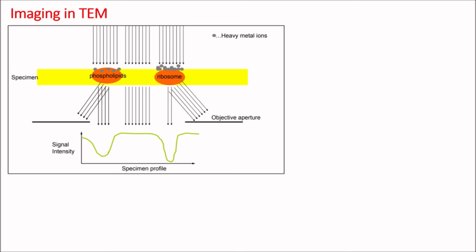Absorption of electrons would result in heat damage of the specimen if it is heat sensitive. At high magnification, at which a small area of the specimen is exposed to high radiation, beam damage is an issue. Heavier elements lead to a much higher interaction and diffraction of the electrons. The main contrast formation is achieved by trapping the diffracted electrons using the objective aperture located in the back focal plane of the objective lens.